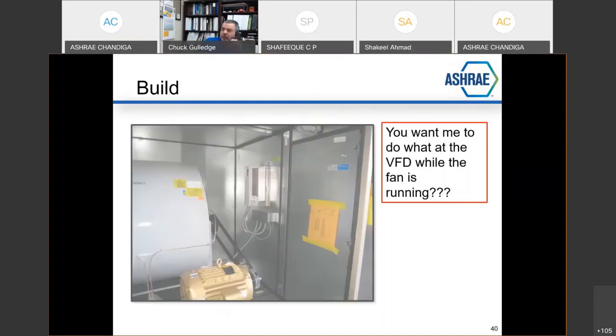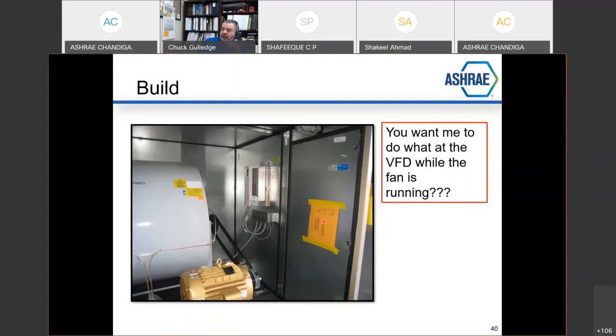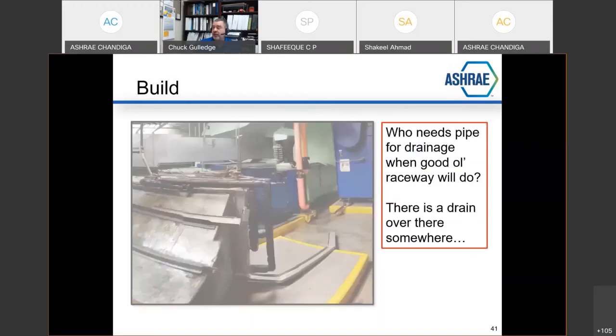Just very impressive. You want me to do what at the VFD while the fan is running? Who here among you would climb into an air handler that's running on a 20,000 CFM air handling unit with this big double width, double inlet centrifugal fan running with a belt and put your posterior up against this to get to the drive to look at it and see what it's doing? Nobody would. This was crazy that something showed up this way. Who needs pipe for drainage when good old Raceway will do the job? Trust me, there is a drain over there somewhere.